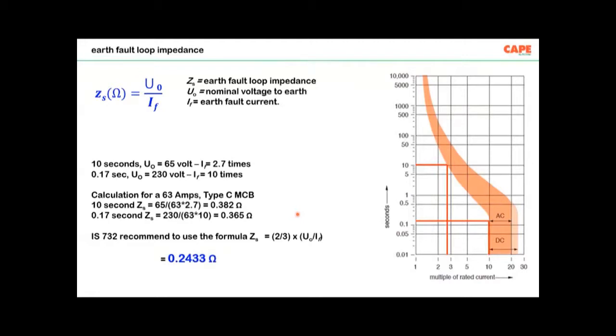Earthed system, as I said, the earthed and unearthed system. In an earthed system, safety is achieved by automatic disconnection of the supply and protective equipotential bonding. For disconnection, there is a maximum time. So within a certain time, you are supposed to disconnect. Otherwise, the fault will create a fire or electrocution.